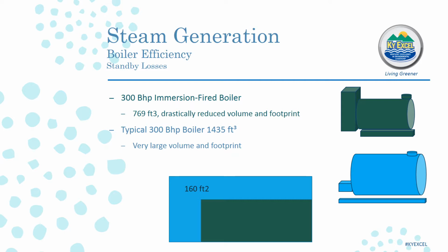Standby losses can also be affected by the boiler design. A dry back boiler with a large refractory rear door will lose more energy than an immersion or wet back boiler.